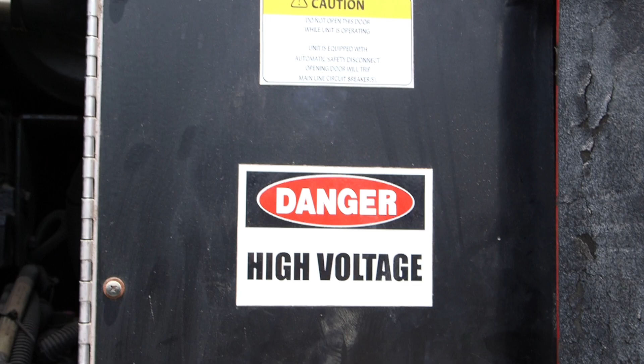For a mobile unit, since it's not an automatic switch, before you connect and kick everything off, make sure all panels are off, the breaker box is off, and all control power is completely off. Before connecting to the application, check that incoming power is in fact off, and that there's a separation between the grid feed and yours if you don't have a disconnect switch.